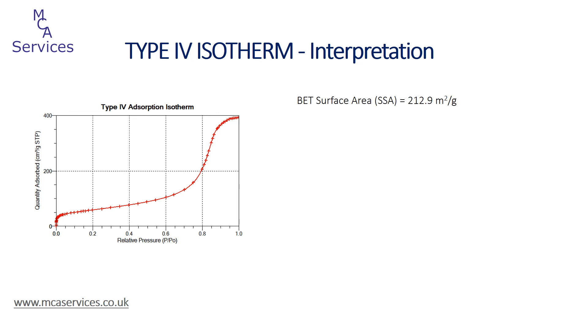We can use this isotherm to calculate the BET surface area of the sample — in this case 212.9 square meters per gram, calculated over the relative pressure range 0.05 to 0.25. From the region of the Gurvich plateau at high relative pressures, we can also calculate the total pore volume of the sample, calculated at 0.62 cubic centimeters per gram of sample at 0.994 relative pressure.